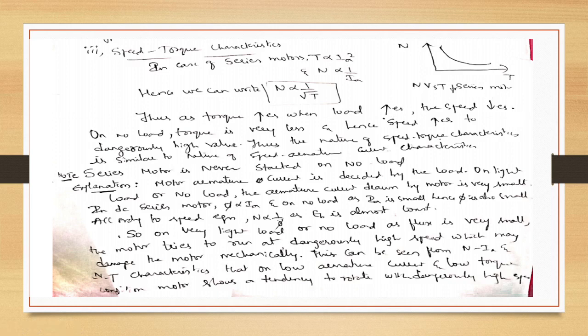All of you note down this very important point. Series motor is never started on no load. In the experiment, also in the laboratory, we have seen that series motor should never be started on no load. Let us see the explanation why it should not be started on no load. Motor armature current is decided by the load. Depending upon the load, how much armature current the motor should take is decided by the load.